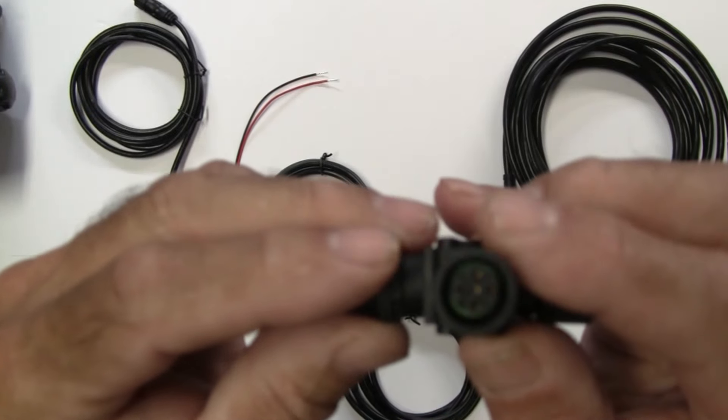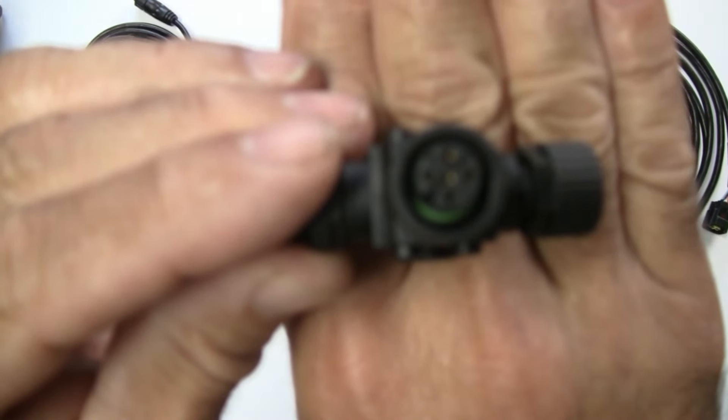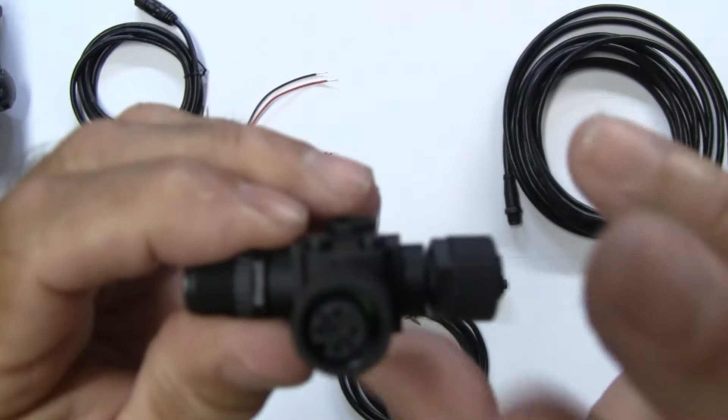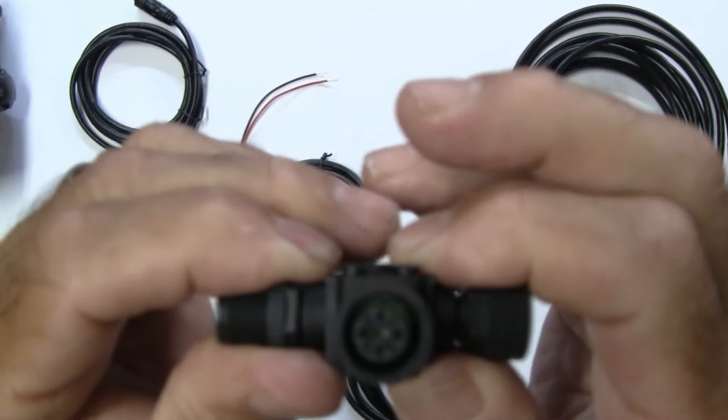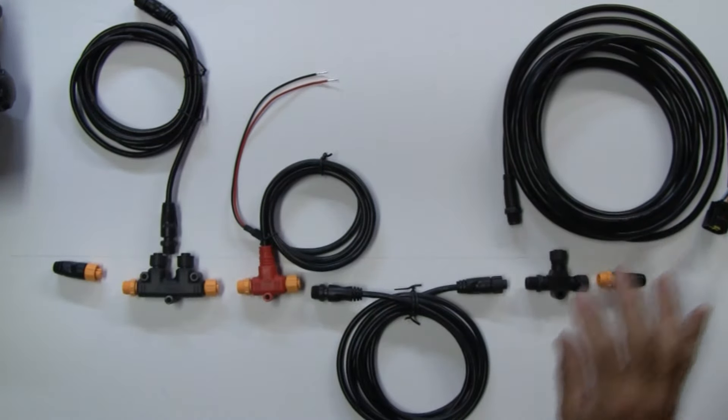It's a five pin connector that's part of the bus. There is a male connector on one side, female on the other, and the top of the T, or the bottom part of the T depending on how you look at it, that's for the drop cable. That's always going to be a female.